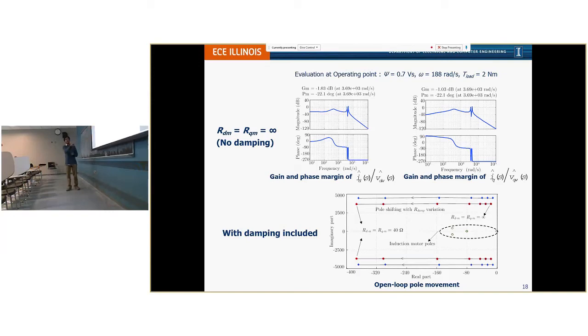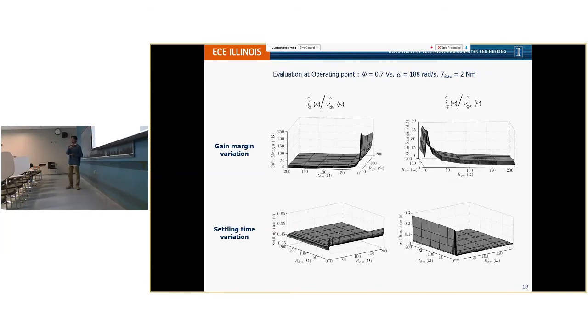When you add this active damping resistance, you see that the pole is shifting towards the left, which means it is giving relative increase in stability, which is good for us. We want stability. This clearly indicates that use of damping is definitely helpful, and the more resistance you include, the more left it would come.